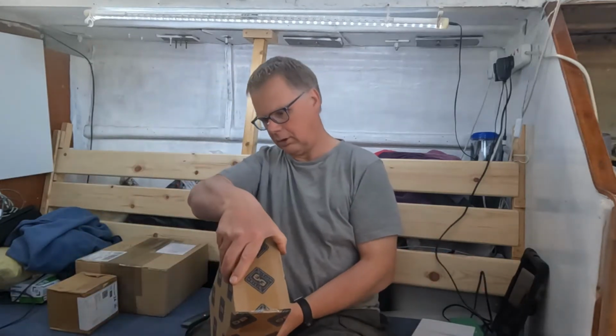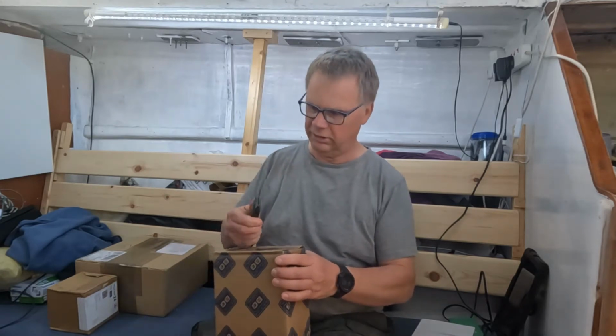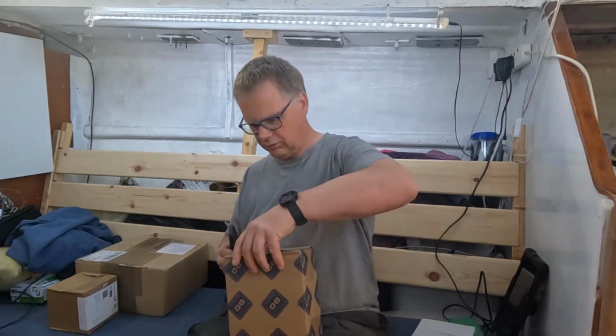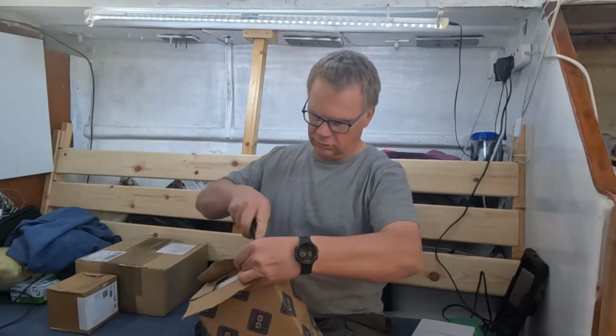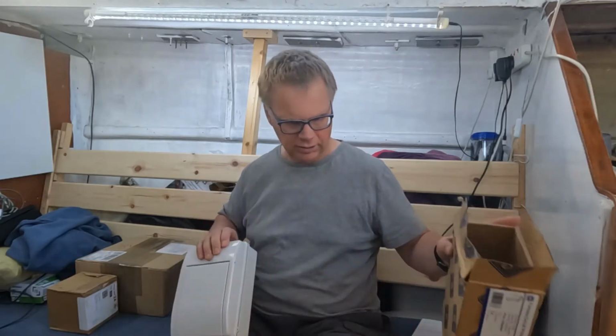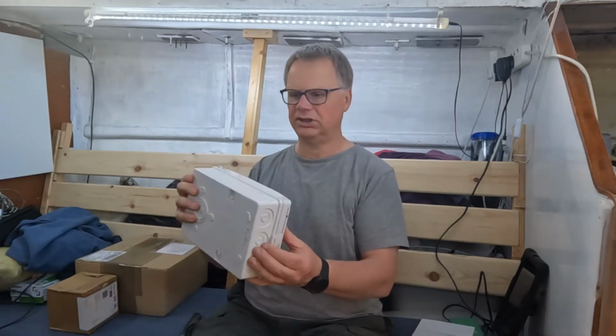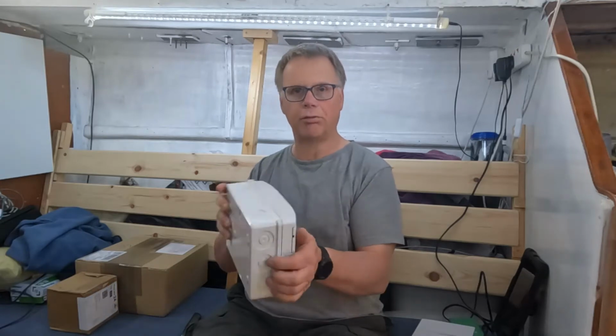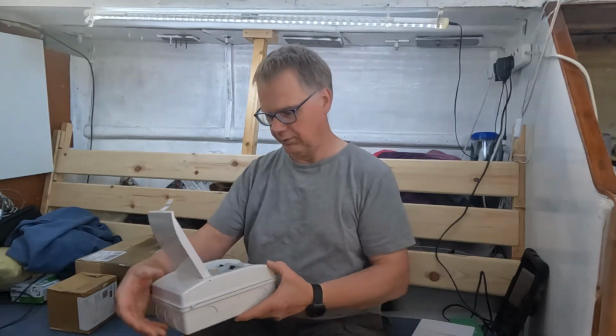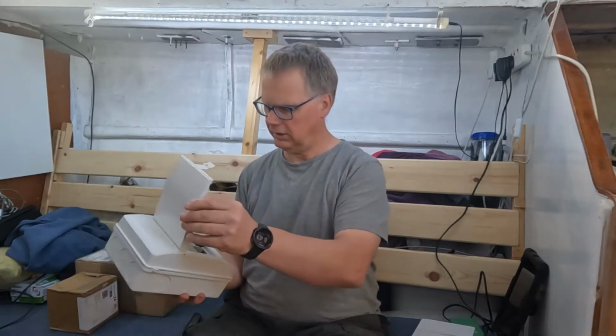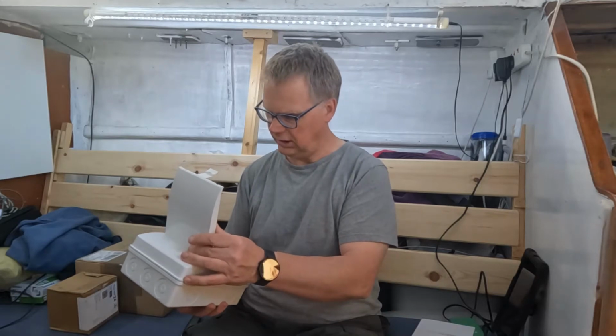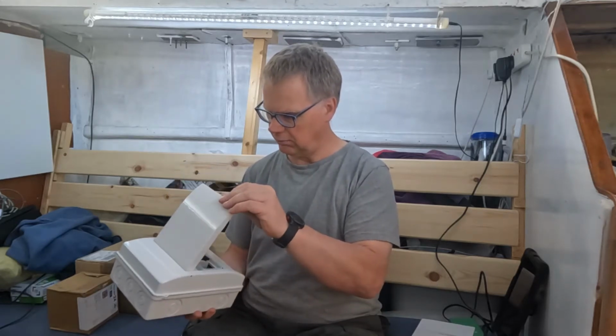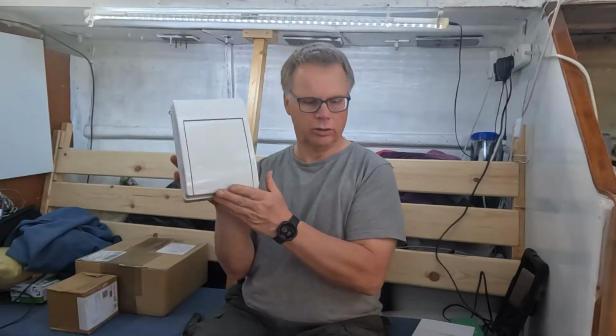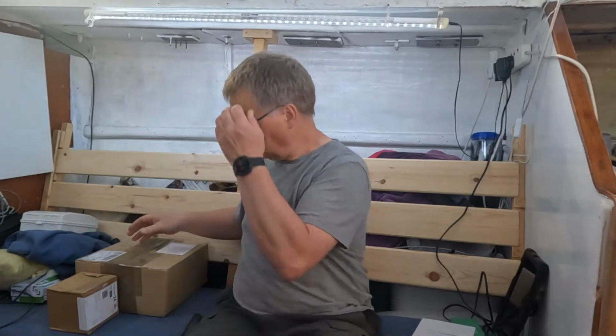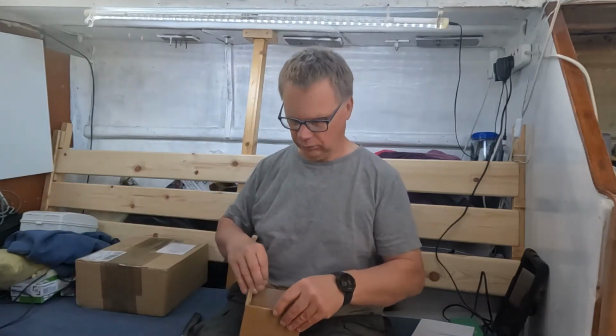Lots and lots of cardboard, and this is what I hoped it was - the consumer unit that will go between the isolation transformer and the multi-plus. It's one designed and approved for showers, so it's supposed to be more waterproof, and it has an RCD and a 63 amp circuit breaker, which is what Victron recommend. That means we'll be fully protected as we ought to be from the shore power.